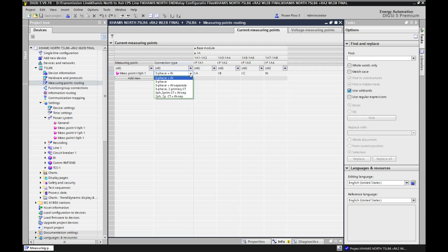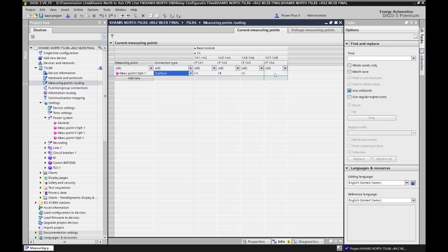Usually our system is three phase plus neutral — red, yellow, blue and neutral — taken from the star point of the CT. We use this option. But for example, where I have a delta-connected CT and I have no neutral, I will select three phase only. If I select this option, as you can see, the neutral disappears — Ia, Ib and Ic only, because we don't have neutral, since the connection type selected is three phase only.